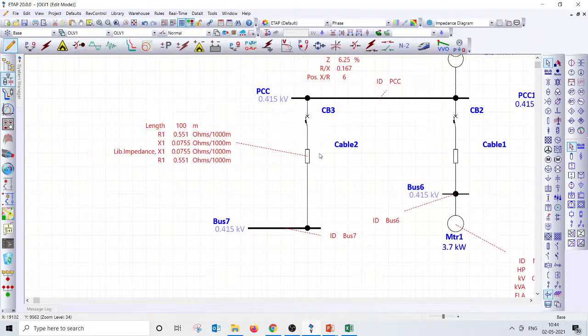So here again you can check the short circuit withstand capability of these cables with respect to the let-through energy of this MCCB and this cable. And most of the times, whenever you have smaller load currents, like if you're going with 63 amps or 100 amps, the cable size requirement will be less, and that cable may not be able to withstand the short circuit current, especially when the cable length is too small.